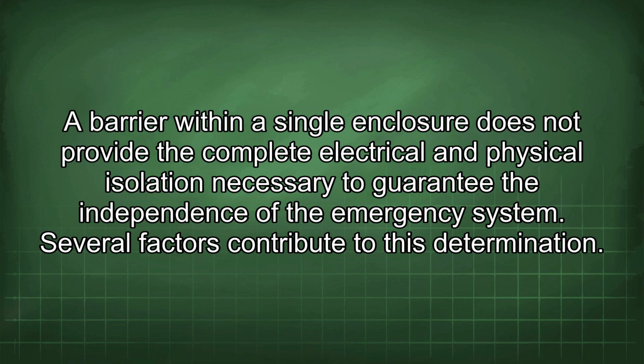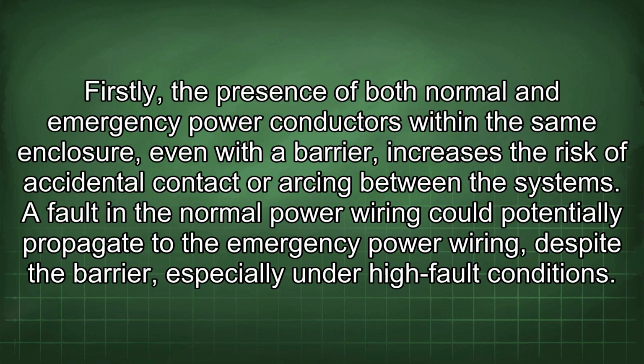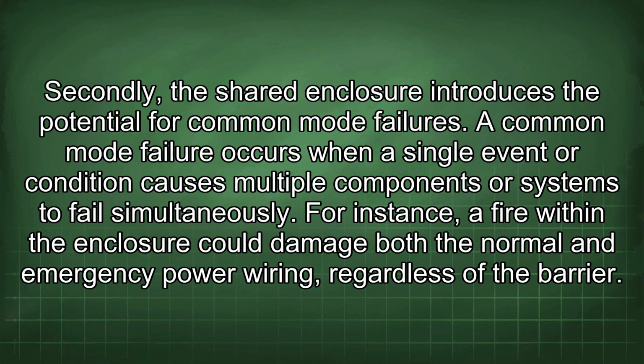Several factors contribute to this determination. Firstly, the presence of both normal and emergency power conductors within the same enclosure, even with a barrier, increases the risk of accidental contact or arcing between the systems. A fault in the normal power wiring could potentially propagate to the emergency power wiring, despite the barrier, especially under high fault conditions. Secondly, the shared enclosure introduces the potential for common mode failures.